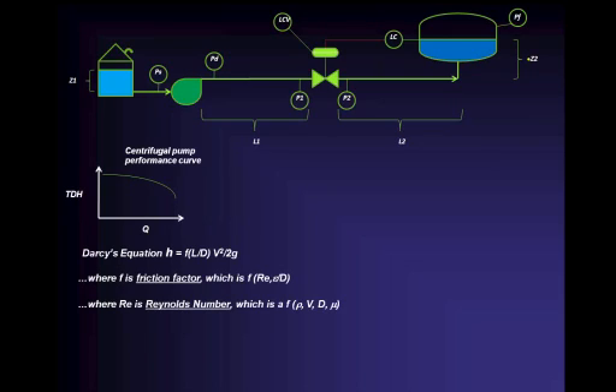Well, this is more complicated because the Reynolds number is a function of rho, the density, V, the velocity in the pipe, D, the diameter of the pipe, and mu, the absolute viscosity of the fluid in centipoise. Maybe you're starting to sense here that we have a lot of interrelated parameters that are going to change as we change other things. Sizing a control valve is a very iterative process. You have to plug and chug, re-plug and chug, re-plug and chug. Thank God we have computers that do that now.